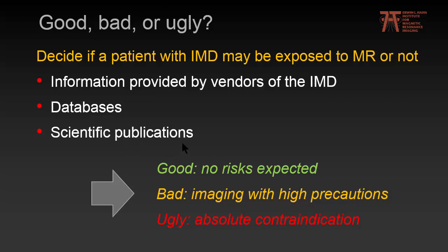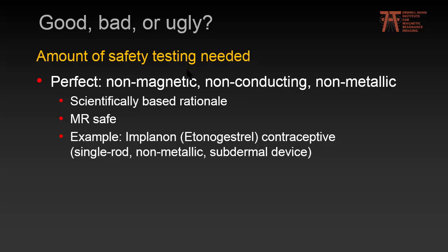Based on all this, we can separate whether an implant is good — where no risks are expected — bad, where imaging may be allowed only with high precautions, or ugly — an absolute contraindication. Good, bad, or ugly can also be viewed with regard to the amount of safety testing needed. I'd like to introduce a fourth group: the perfect implant — non-magnetic, non-conducting, non-metallic — for which a scientifically-based rationale is adequate to say it is MR-safe.